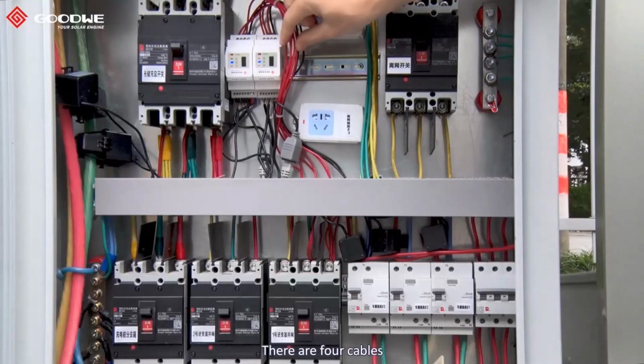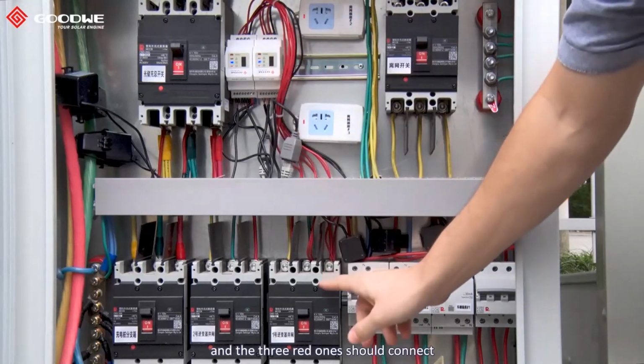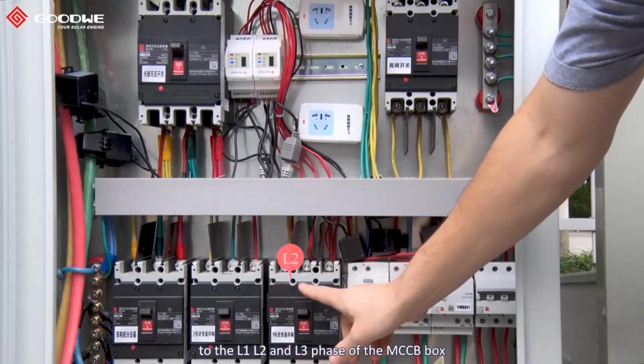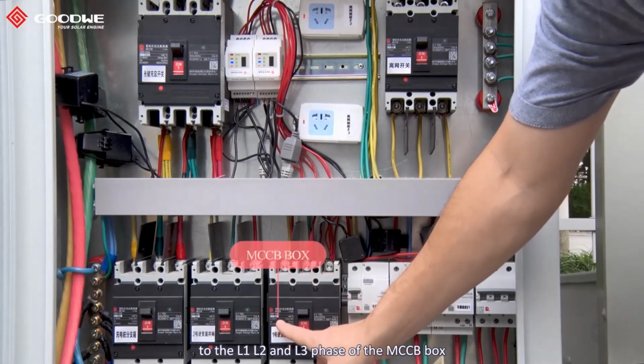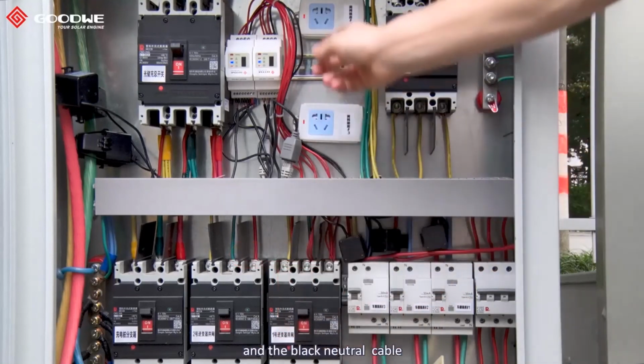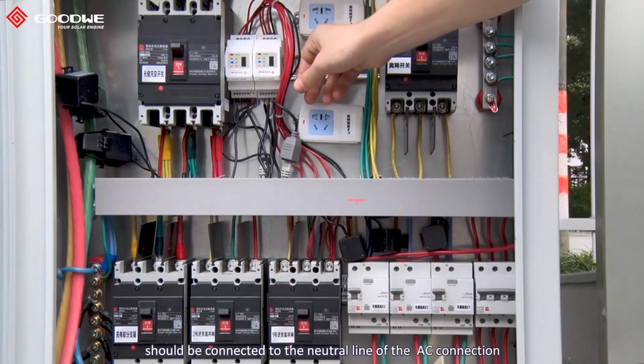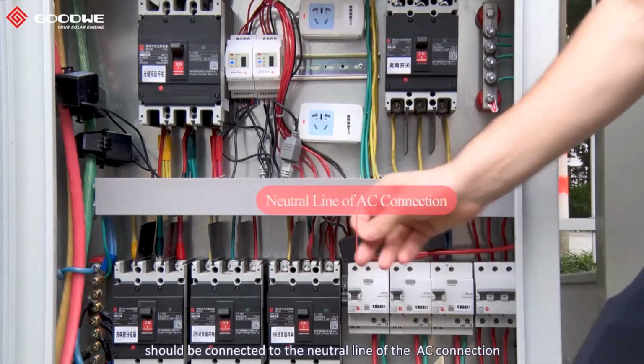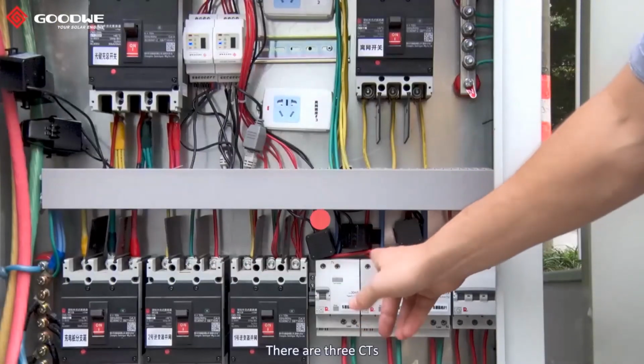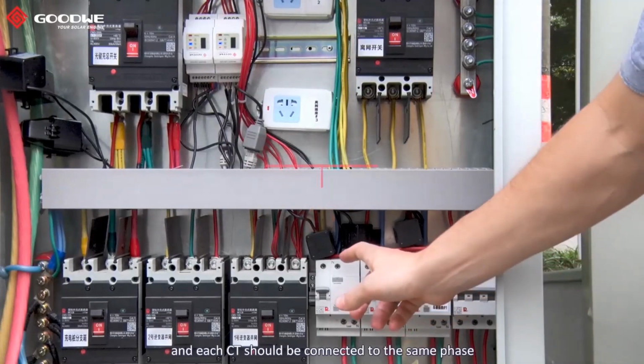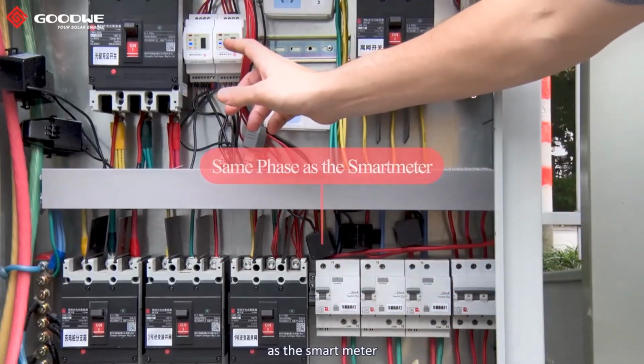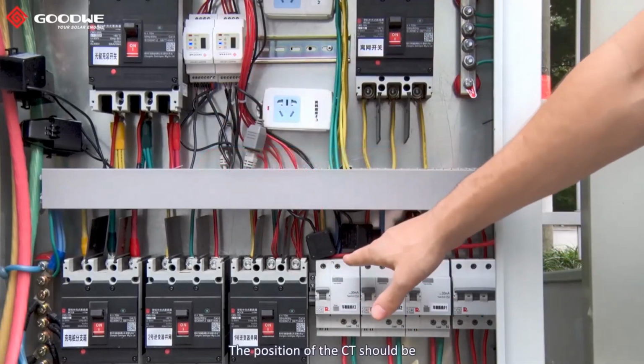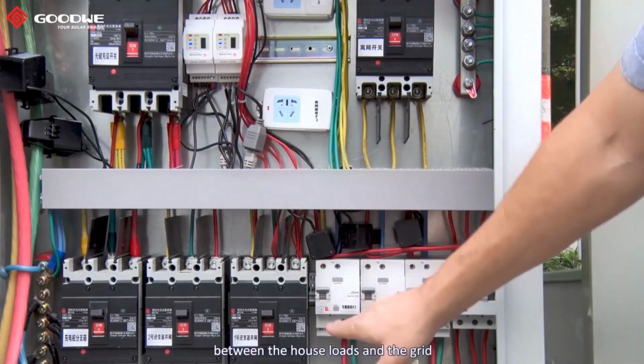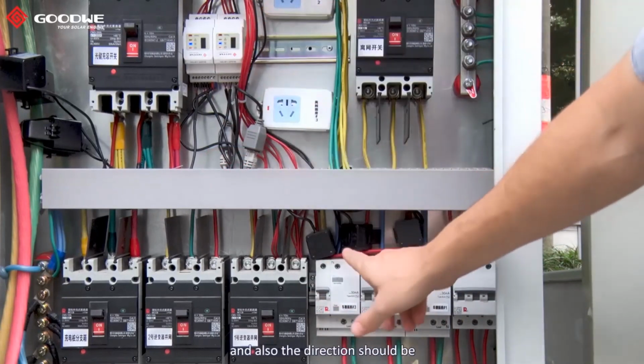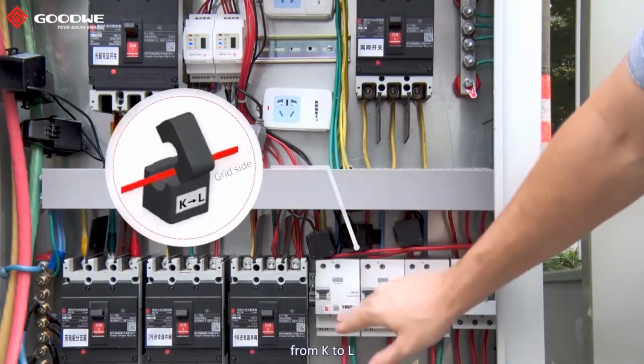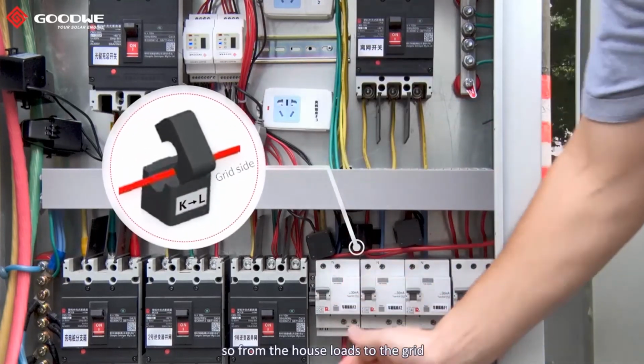There are 4 cables, and the 3 red ones should connect to the L1, L2 and L3 phase of the MCCB box, while the black neutral cable should be connected to the neutral line of the AC connection. There are 3 CTs, and each CT should be connected to the same phase as the smart meter. The position of the CTs should be between the house loads and the grid, and the direction should go from K to L, so from the house loads to the grid.